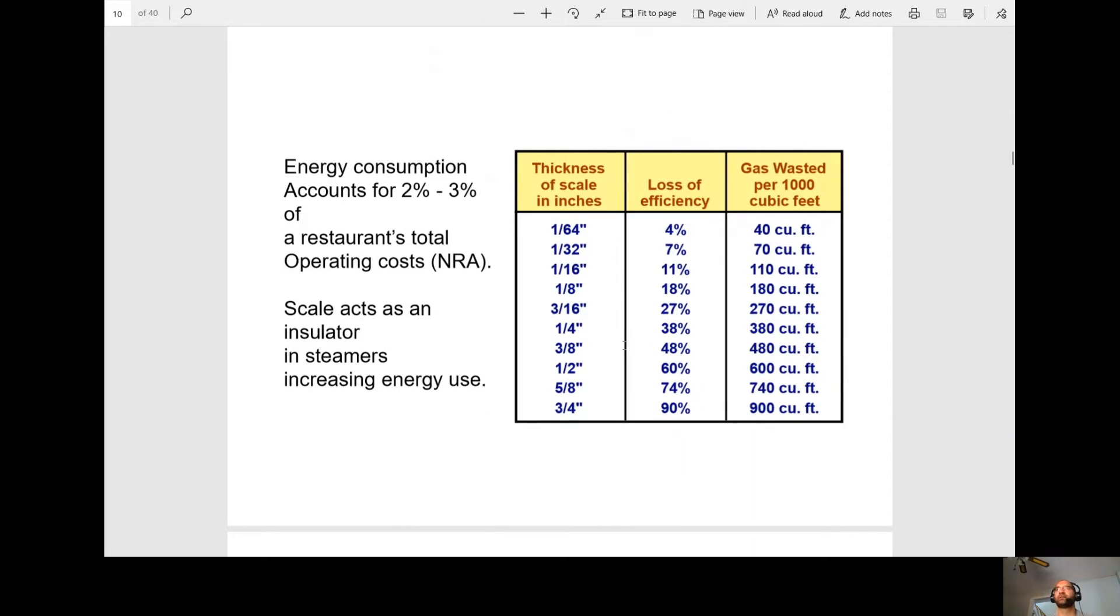So here's just one thing that you can kind of explain to the customer why scale buildup's bad. Obviously, energy consumption, so scale acts as an insulator, so it's around the element, it's around the tank, we can't really heat the water directly. So based on the thickness of the scale, if you have three quarters of an inch, it goes up to 90% loss of efficiency. So you'll find that that boiler will probably be running almost the entire day. A good indicator of that is when you fire it up, it takes forever to get to temperature, to your set PSI.